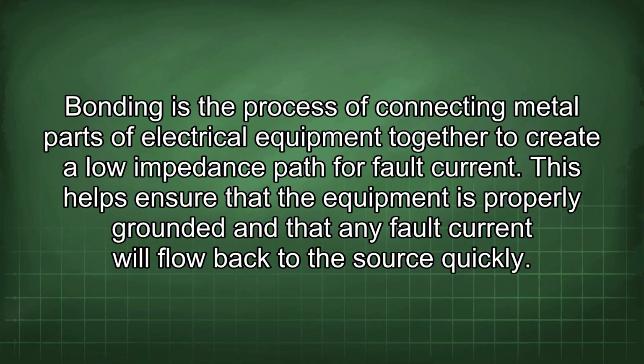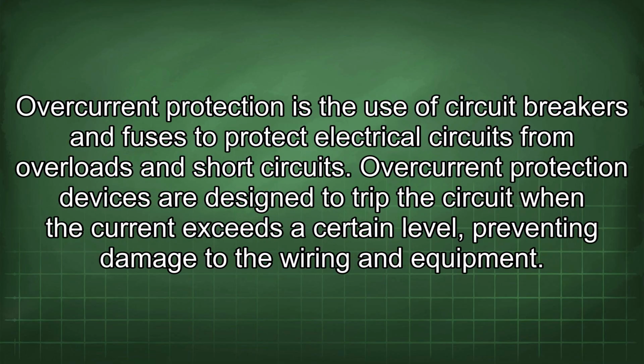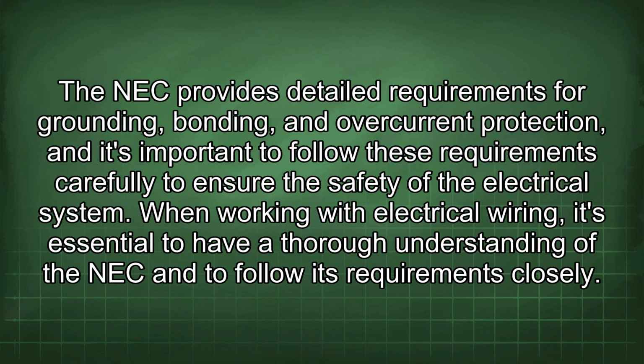Bonding is the process of connecting metal parts of electrical equipment together to create a low impedance path for fault current. This helps ensure that the equipment is properly grounded and that any fault current will flow back to the source quickly. Overcurrent protection is the use of circuit breakers and fuses to protect electrical circuits from overloads and short circuits. Overcurrent protection devices are designed to trip the circuit when the current exceeds a certain level, preventing damage to the wiring and equipment. The NEC provides detailed requirements for grounding, bonding, and overcurrent protection, and it's important to follow these requirements carefully to ensure the safety of the electrical system.